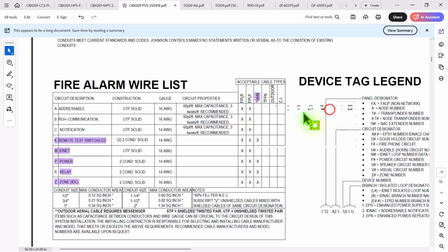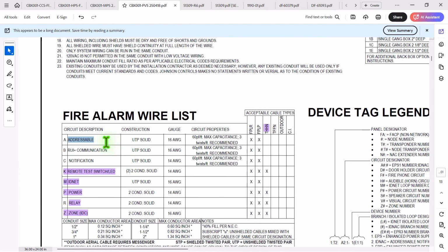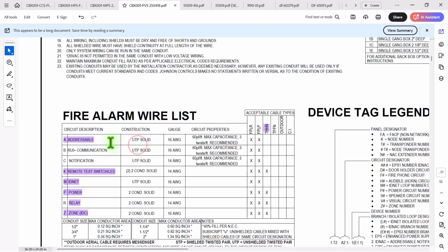So the only cables we should be using are the 16. The addressable is going to be for all the pull stations, heat detectors, smoke detectors, relays - everything on the right side, the tamper switches, that's what the addressable is for. And we could change that to data, so we change that to data.